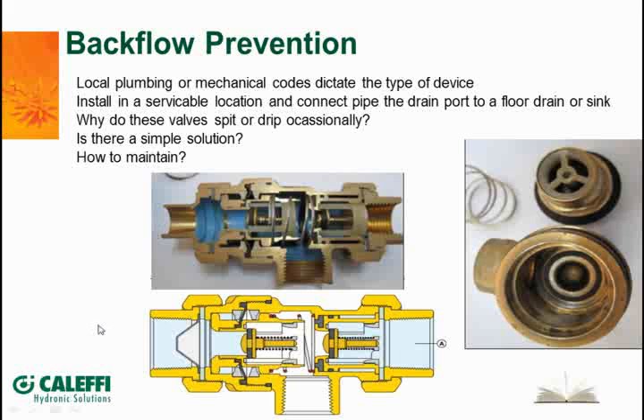So basically what happens when the fluid comes into this device, as you can see, we've got a port here that goes right to atmosphere because that's where the water is going to come out of it. It's going to go down to the floor when it comes out of the boiler, so it doesn't go back in the system. The first thing that has to happen when the water comes in, you'll notice there's a little, let's call it a spool inside here. It's this little part right here. So when the pressure comes in from your water system, it's going to slide this spool and make a seal right here. This is actually the cutaway end view of an O-ring. I don't know how much of you can see it in the cutaway picture, but this little brass surface right here is going to slide and go against this O-ring seal.